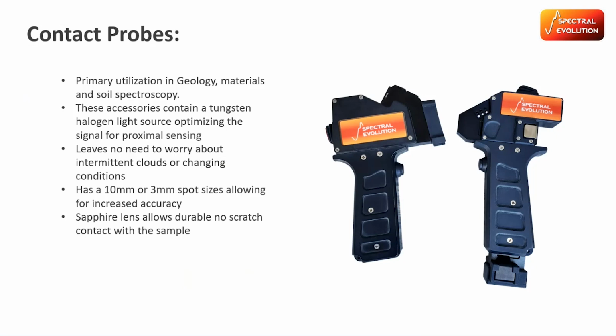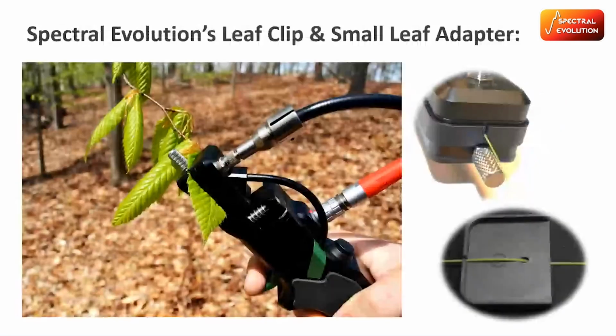And so that's a great way to eliminate any field conditions, is to use a contact probe, because your signal will always be the same or be consistent, and you won't have to worry about any changing conditions out in the field. We also have our leaf clip. This can be integrated on the Naturaspec Plus as well as our new pine needle adapter. And so this will let you get scans of any kinds of materials that may be sensitive, like vegetation. So we have our light source integrated into the handles so that it doesn't send any of the thermal signal that may dry out a leaf or manipulate a sample in any way. So this is great for repeatability and characterizing things that are in your ground truthing and speciation and vegetation health.